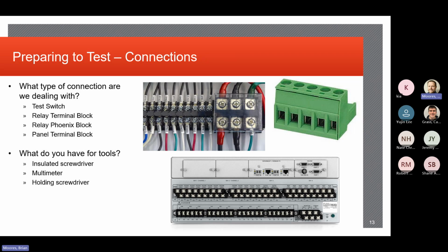SEL does offer another type of connection called a connectorized plug, which just plugs into the back of the relay. It's kind of a hybrid. It's not a green plug like that. It's a lot more robust. CMP used those for quite a while. I think they've gone away from them now. But you could really just unplug those and plug a test lead directly into the back. So it was almost like those screw terminals didn't exist. Instead, there's wires on them, and you could just take that whole black plug in or out.